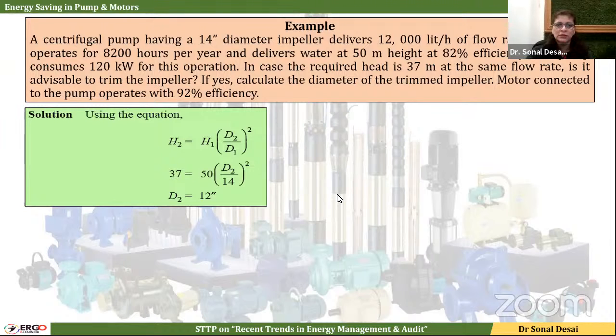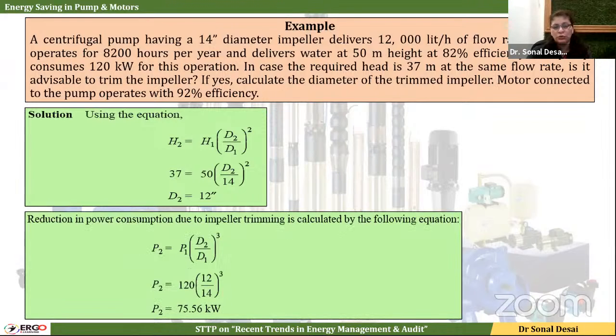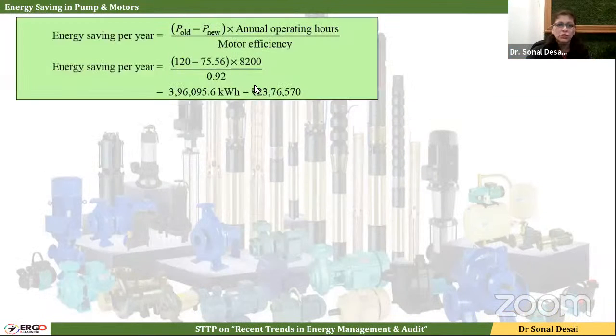Is it advisable to trim the impeller? If yes, then what diameter should it be trimmed to? Initially it was 14 inch, and now with the requirement of 37 meters of head, the new diameter is 12 inch. With the change in diameter, you can see that 120 is directly slashed down to 75 kilowatts. So if you talk of energy saving per year, it turns out to be around 23 lakhs of rupees.